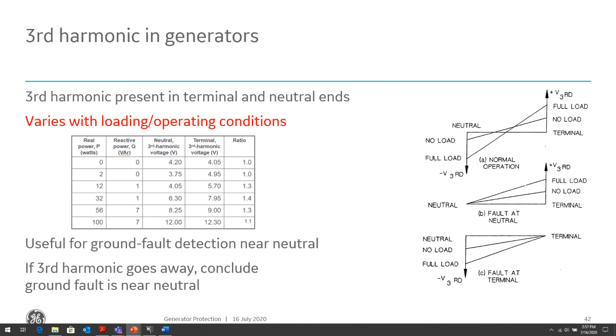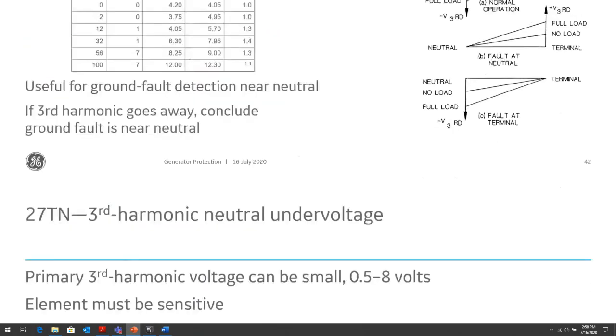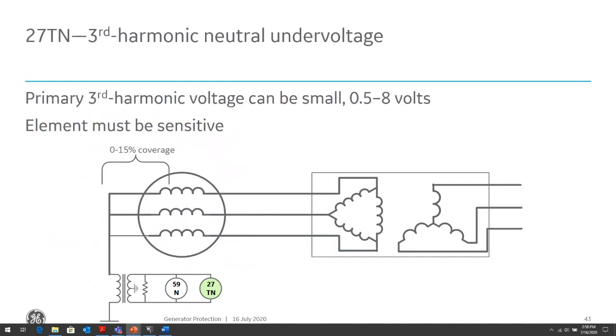Now, the problem with the third harmonic method is how to determine what level to set the pickups at, what undervoltage level to set. It's very difficult to set because we don't typically know what that third harmonic voltage is. We can empirically calculate it and determine it, but we're never going to know for sure what it is until we run the generator. So we might need to run the generator, take some measurements, and see what the harmonic voltage is. Not only that, that third harmonic voltage changes based on loading on the generator and the power factor of the generator. So the distribution of the third harmonic voltage changes as the operating condition of the generator changes. That makes it very difficult for us to reliably set a 27TN element to be able to reliably detect ground faults.